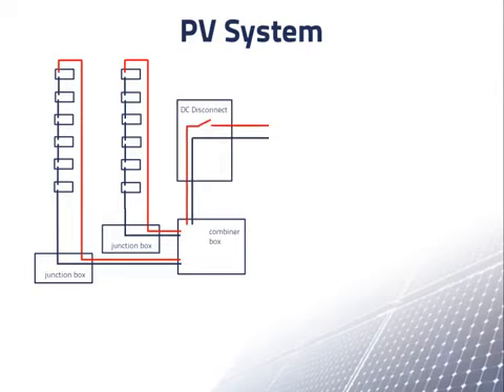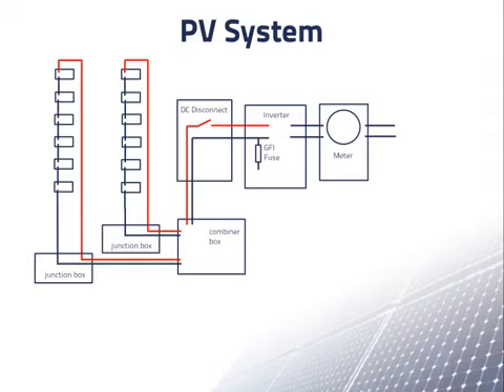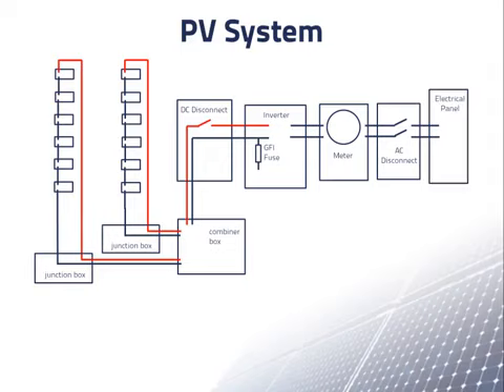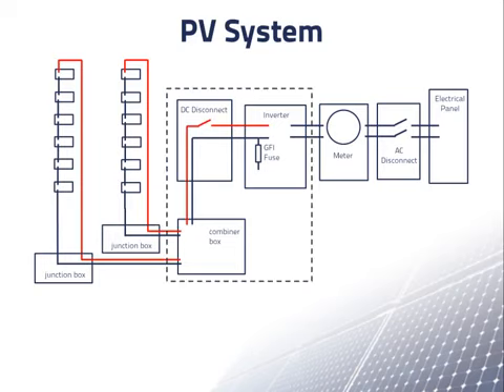We'll wire from the combiner box to a DC disconnect, and from there to an inverter. This is a grounded system, so in the inverter we have a GFI fuse to ground from the negative output of the array. On the AC side of the inverter, we have an output meter and an AC disconnect. From there, the power goes to the electrical panel of the building. As we've seen in many systems, the combiner box, the DC disconnect, and the inverter are in the same enclosure.